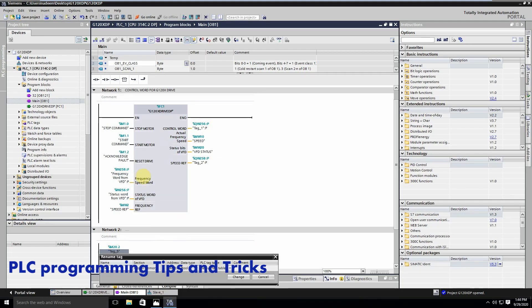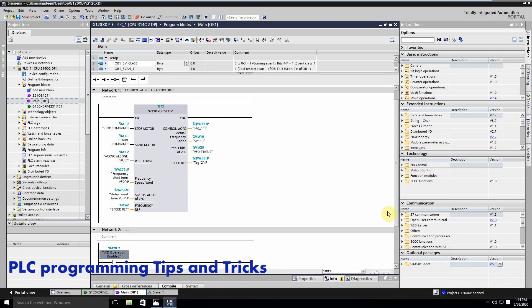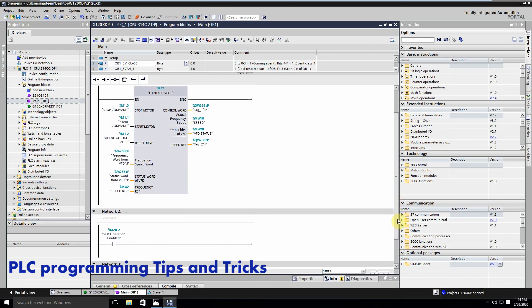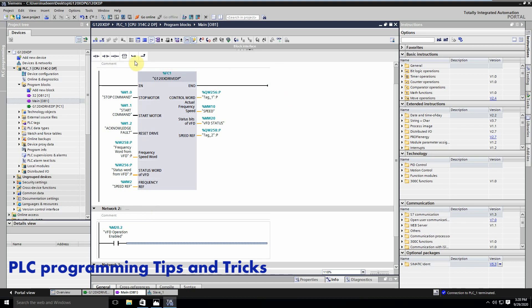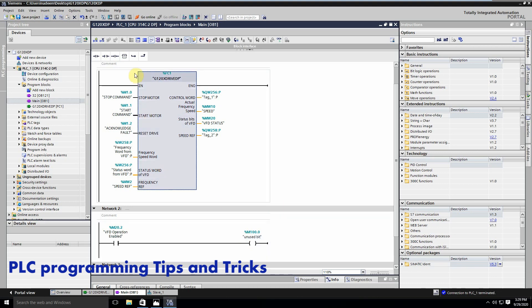We are using M20.2, which is the operation enabled bit, and we can rename this tag as 'VFD operation enabled'. To complete this rung we put a dummy coil at M100.0. Now we are ready and we will load this program into the PLC.